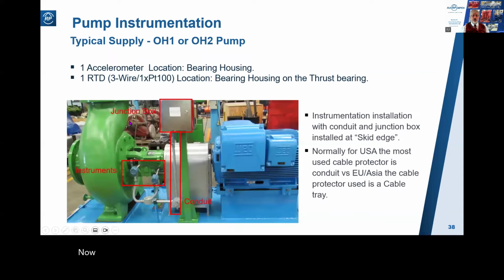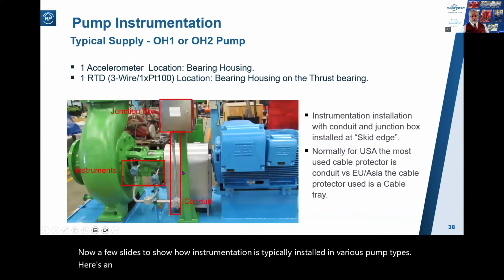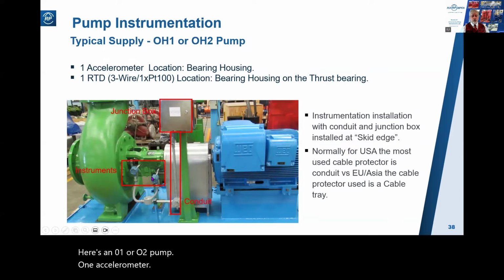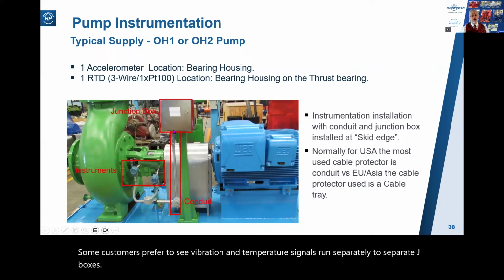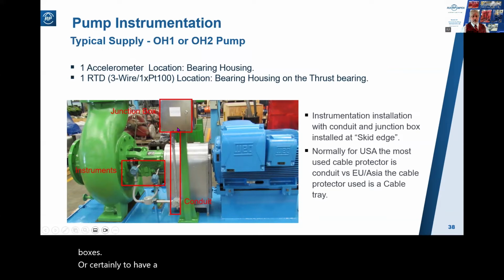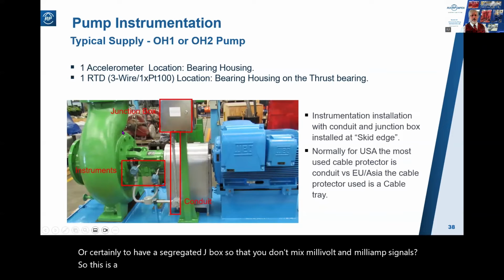Now a few slides to show how instrumentation is typically installed in various pump types. Here's an OH1 or OH2 pump, one accelerometer, and one bearing RTD. Wired to a J-box, and in this instance, the wiring is run in conduit. Now, some customers prefer to see vibration and temperature signals run separately to separate J-boxes, or certainly to have a segregated J-box, so that you don't mix millivolt and milliamp signals. So this is the most common instrumentation on an OH1 or OH2 pump.